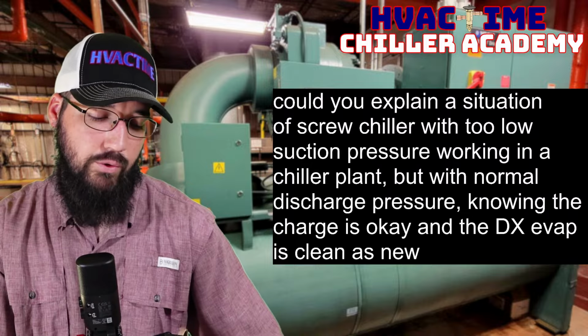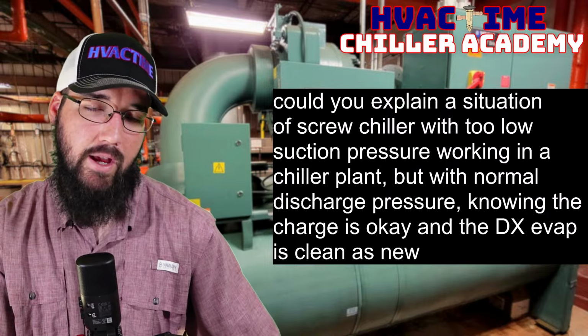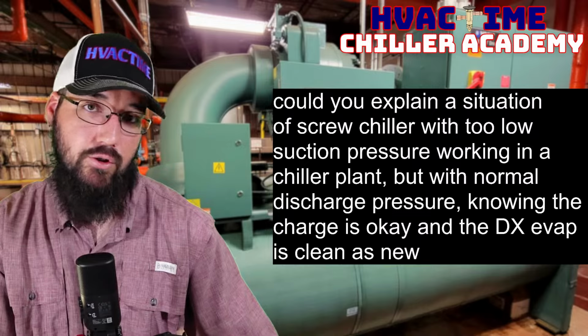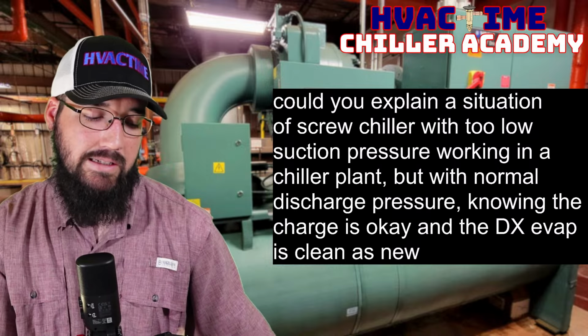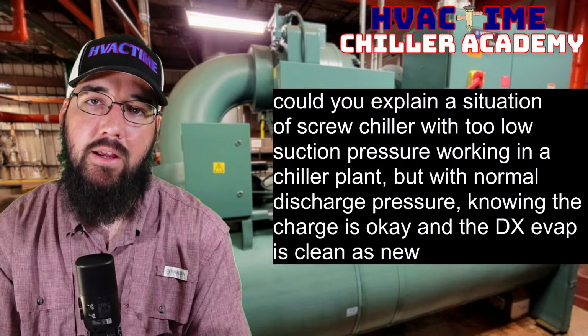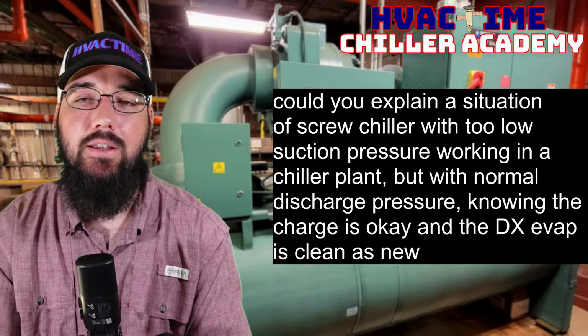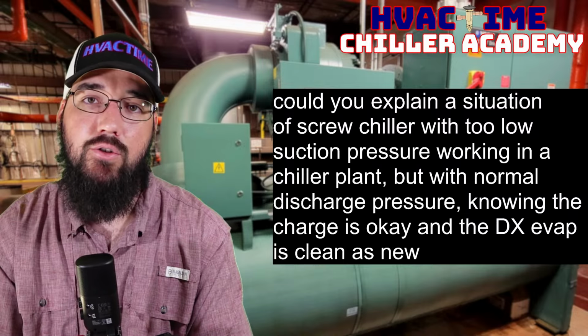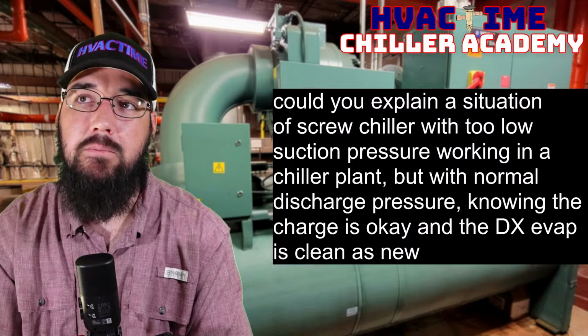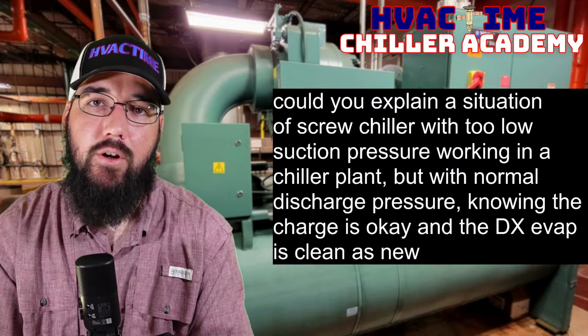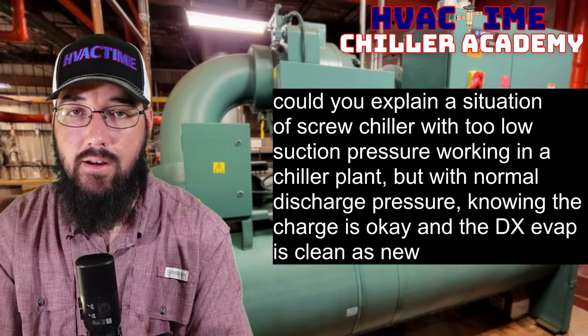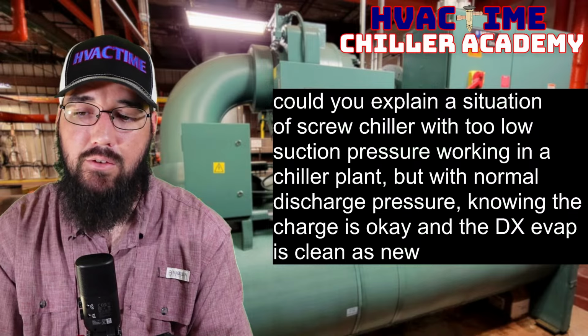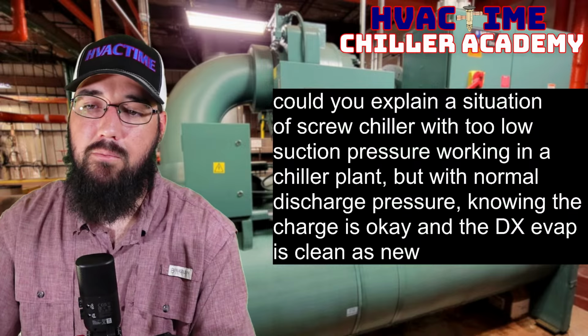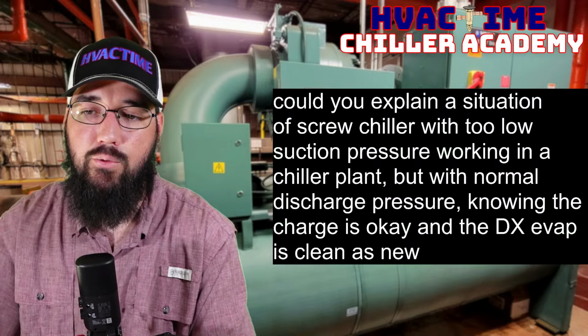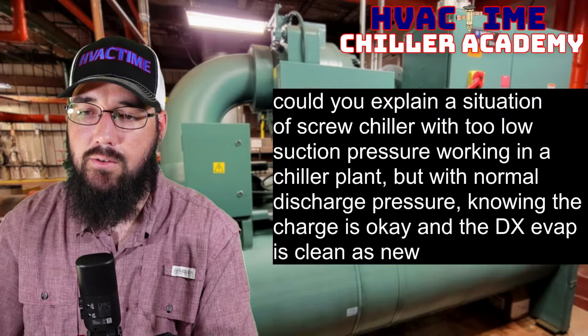So when you see a scenario where you have a low suction pressure but your discharge looks normal, keep in mind the fundamentals of what is making that condenser and that discharge pressure work, and why the pressures are what they are at that given time. It is a very, very important fundamental that we have to keep in mind in this process.